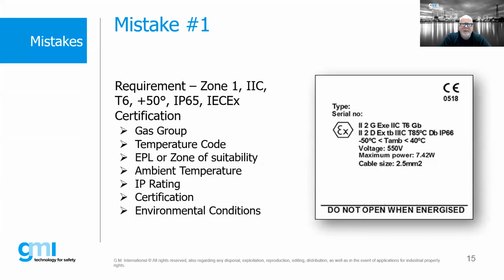So if we look at this label as an example, right? The requirement under the project is Zone 1, IIC, T6, +50, IP65, and we require IECEx certification. By looking at that label, we see a couple things here. We see that our ambient upper end is only rated at +40. However, the project requirement is +50. And if we look at this very closely, we don't see the ATEX cert, but the EX hexagon and the CE mark are telling us that that is ATEX. So this may or may not have IECEx certification, so we may have to do some further investigation before we start using it.